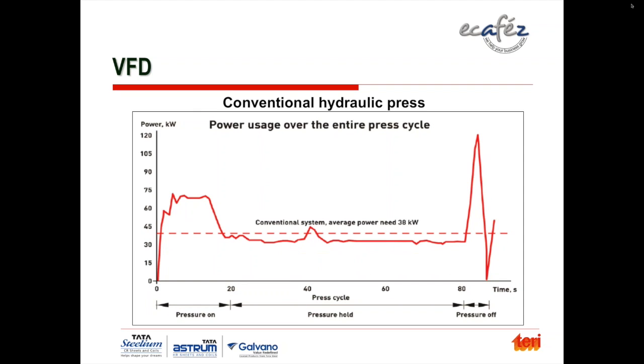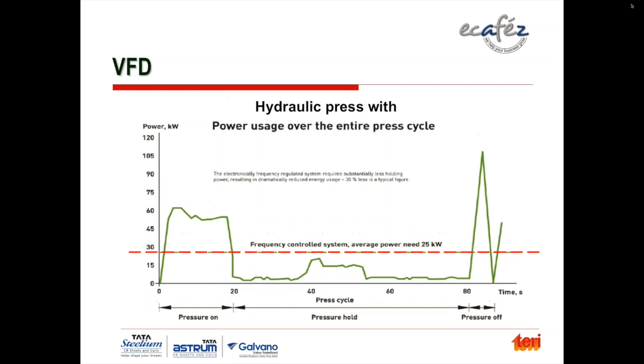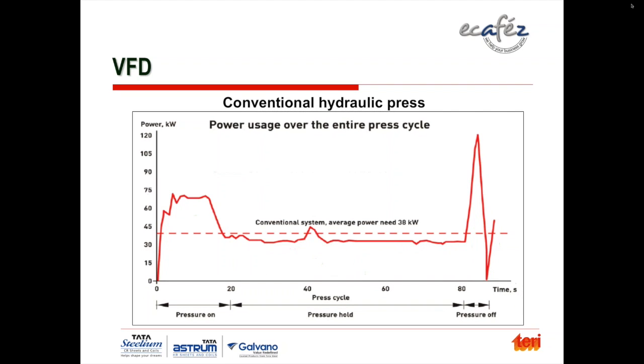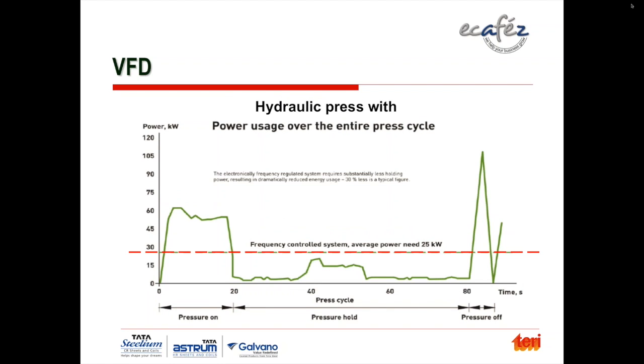Whenever the pressure is not on the sheet, it has basically reduced the power to almost zero, near zero, with the frequency control. The average power needed in this is 25 kilowatts, and previously it was 38 kilowatts average power needed in the conventional system. So this also is a very good option, at least for bigger kind of machines, installation of a VFD to control the power consumption, and it can typically reduce energy consumption by about 30% from the conventional.